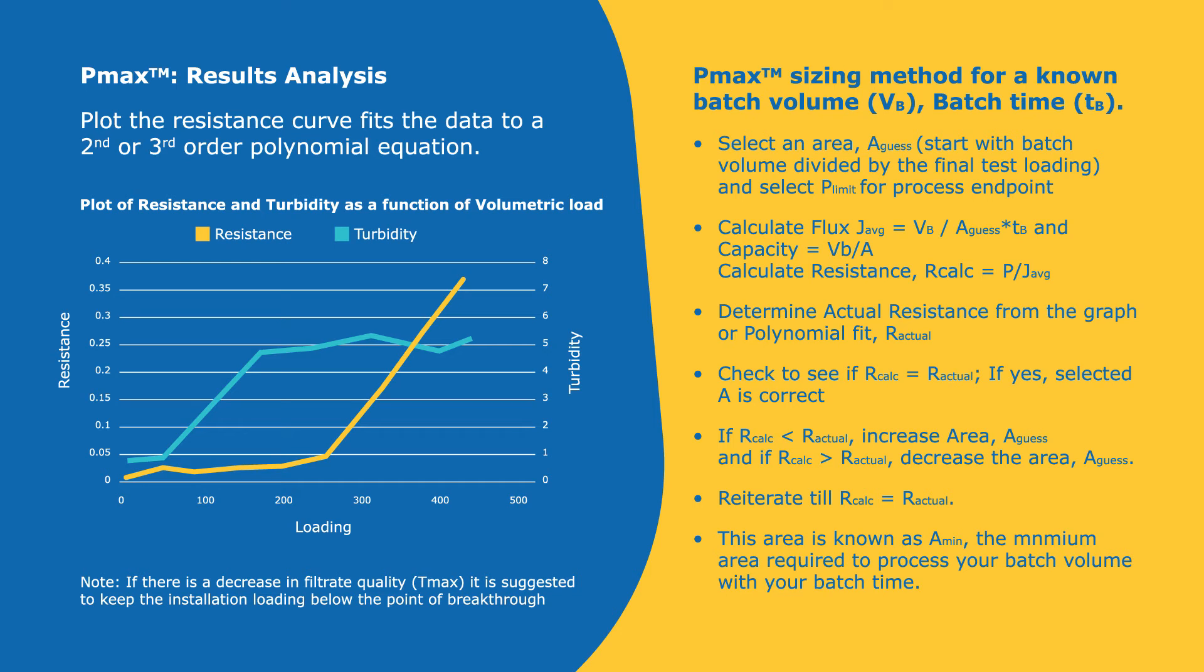So you would have a known batch volume and a known batch time. You would select an area, which we will call a guess. A good first guess would be starting with your batch volume divided by your final test loading. You would select a pressure limit for a process endpoint. So typically if you have two or three processes in a train, two or three filters in your process train, and your maximum pressure for that part of the operation was 20 to 30 PSI, it would be a good starting point to just divide it by the number of filters that you have in your train. So say you have 30 PSI and you have three filters in your train, I would say start with 10 PSI.